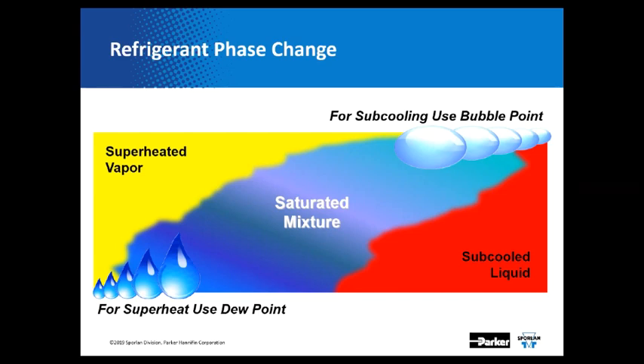I want to briefly discuss dew point and bubble point. Many of the new refrigerants today are mixtures — a blend of different refrigerants in specific proportions — and what happens with blends is they condense and boil at different temperatures. They start to boil at the bubble point and finish boiling at the dew point. The easiest way to use PT charts for a blend refrigerant that has glide: anytime you're measuring superheat, use the dew point; if you're measuring subcooling, use the bubble point.